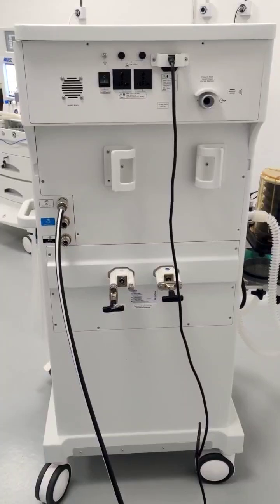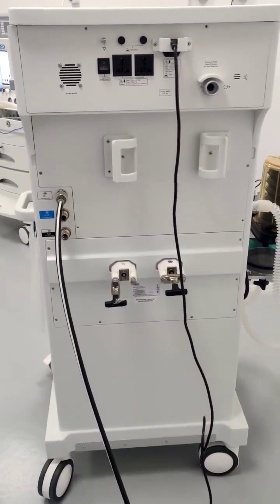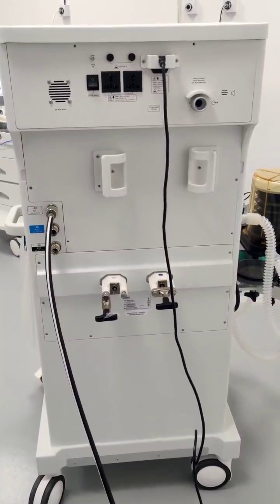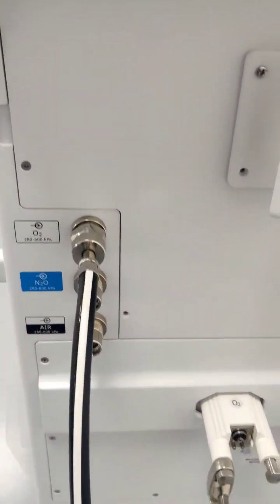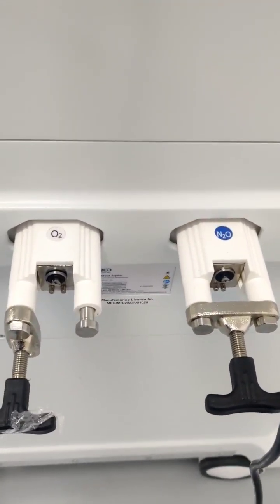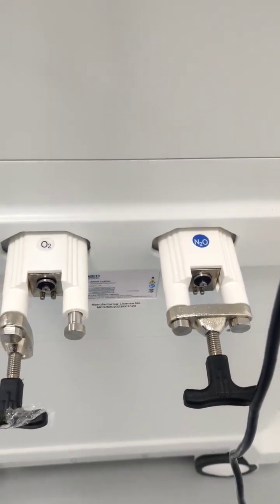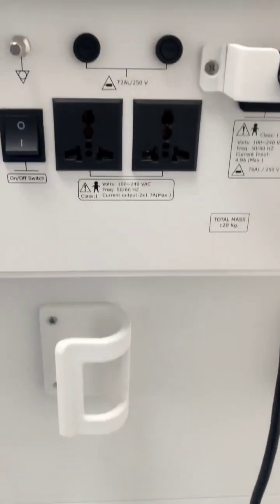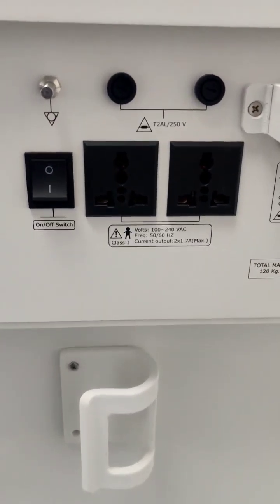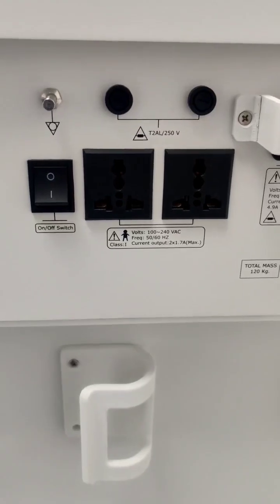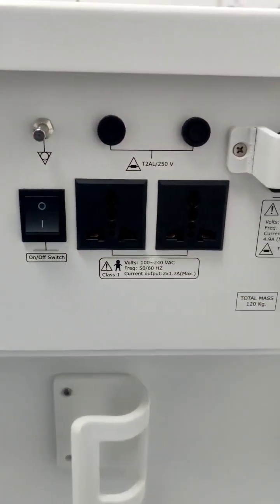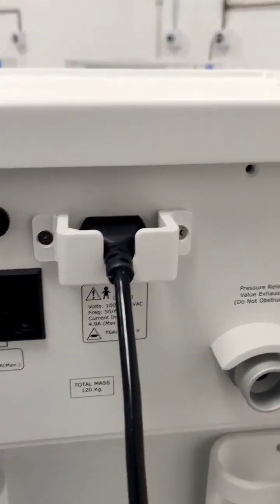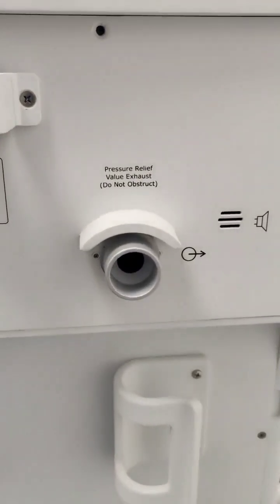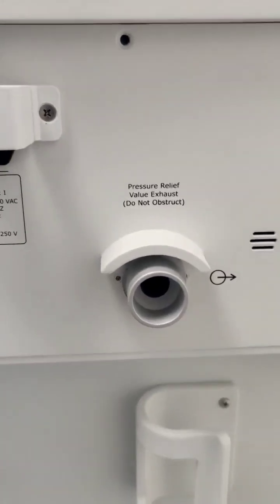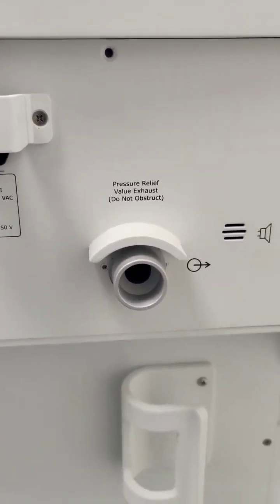So coming on to the rear view of the machine, we are giving 3 pipeline inlets, which is NIST. One is for oxygen, the second one is for nitrous oxide, and the third is for air. And we are giving 2 yokes, one for the oxygen cylinder and one for the nitrous oxide cylinder. Both of these are pin indexed, and at the back side we are giving auxiliary outlets for operating any of the monitors or any device, and we have a dedicated switch for the AC of that. For connecting the power cord, this is the connection over here, and at the back side itself we are giving the exhaust port through which the exhaust gases or the anesthetic gases will be exhausted from the machine.